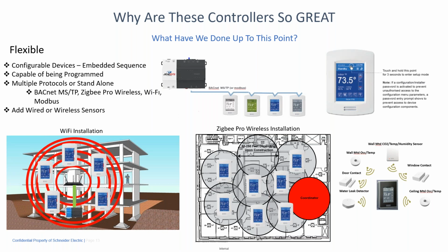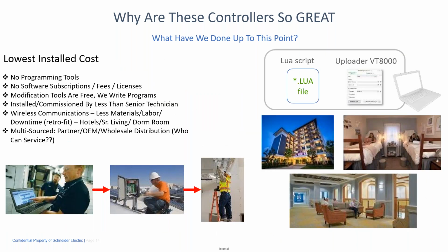And again, it's very flexible in that you press and hold at the top part of the screen, and you go through your configuration parameters to configure the controller to fit your piece of equipment. And finally, what we like to think about these guys is the lowest installed cost, right? There's no programming tools for these, right? It's all done through the face of the controller. If you do choose to modify it with Lua script, then you would load a program into it, but you can still have control over that Lua program from the touchscreen interface.